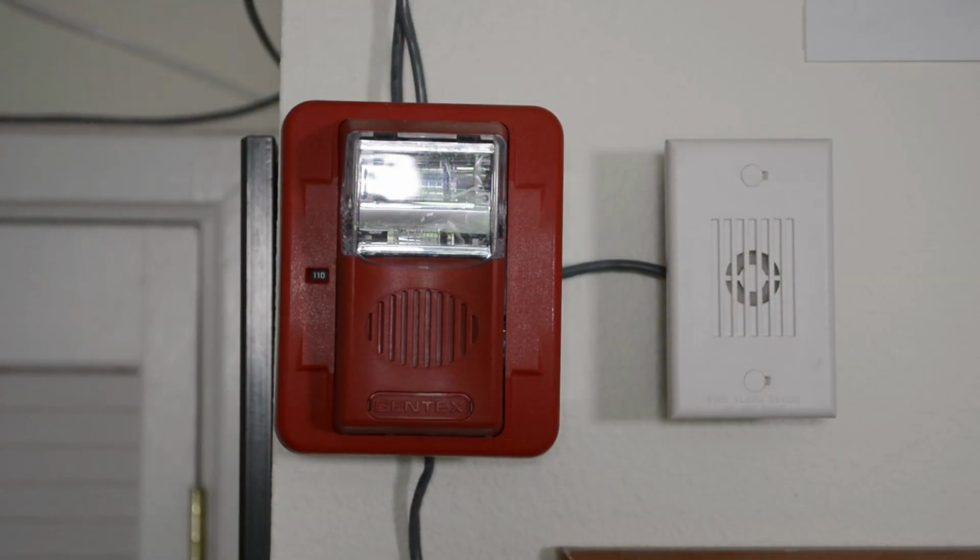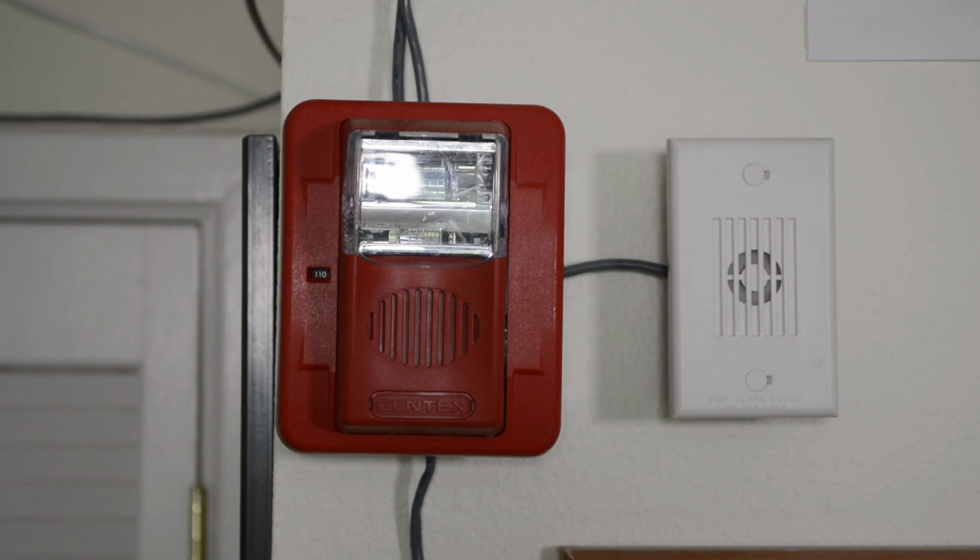Alright, we're back on the big camera. Let's go ahead and give California code on 2400 Hertz another try here. See if maybe this time the pull station and the panel will work correctly. So yeah, it's got an interesting little shift there. Alright, pull station's reset. Okay, let's move on to the next tone here.